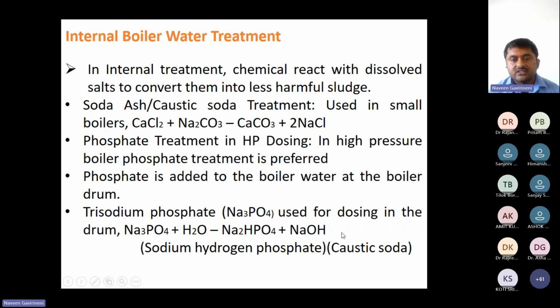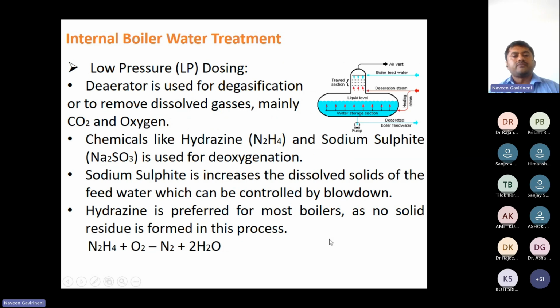And NaOH, the caustic soda, is responsible for increasing the pH, so it is useful for us. There is another internal boiler treatment, for which we use hydrazine, N2H4. Sodium salts were also used, but not nowadays because of solids deposition, and we would have to give frequent blowdowns. Blowdown also causes a loss of heat, so as per the OEM we are not supposed to give blowdown at regular intervals.